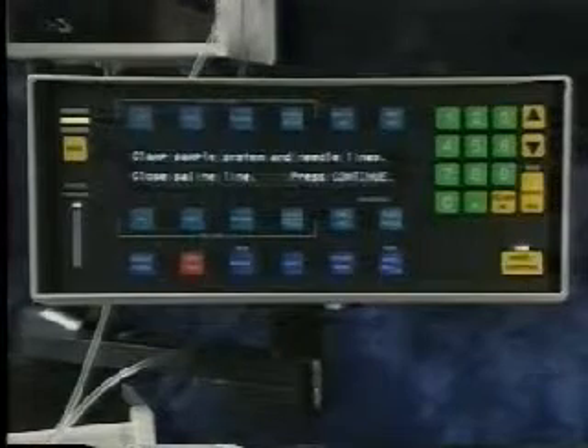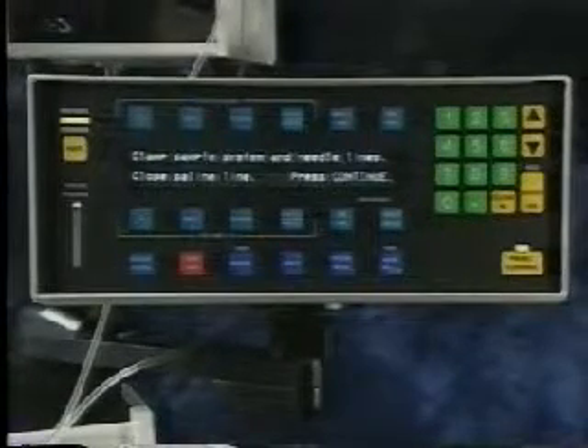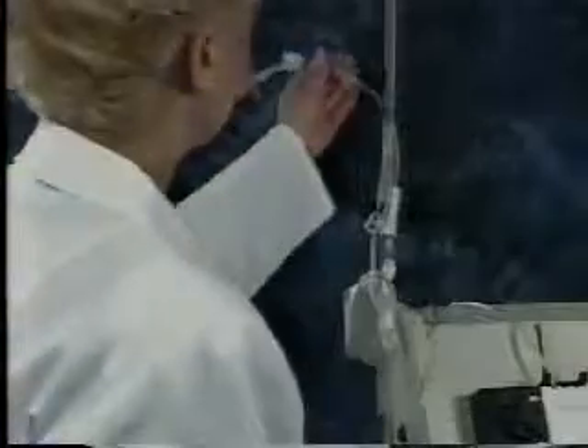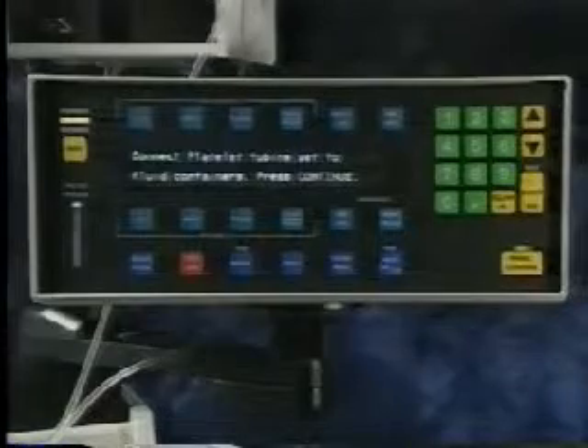The system will instruct you to clamp the sample system and the needle lines and close the saline line. To do this, simply close all pinch and roller clamps except the white pinch clamp at the access manifold. You will close 4 of the 5 clamps as demonstrated here. Press the Continue key and the system will instruct you to connect the fluid containers. Anticoagulant and saline must be obtained from your supplies. Consult your operator's manual for the proper solutions.